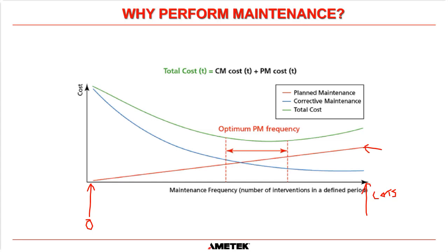And then the blue line here, as you can see, is corrective maintenance, and the green line is the total cost. So if you're not doing any maintenance on the left-hand side here, the total cost, which is the green line, is at its highest. What they're saying is you're not doing any planned maintenance, so the corrective maintenance is at its highest at that point and costs a lot of money. And then as you move to the sweet spot, which is this point here, the planned maintenance goes up to a suitable level where you're in this sweet spot of the curve where the total cost and the corrective maintenance are going down, at their lowest point. Okay, so that's the sweet spot we want to get into.